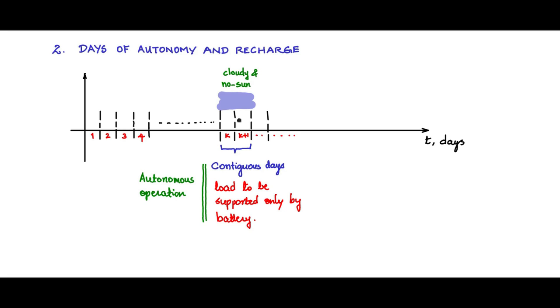It means it is operating by itself without the help from solar or the PV. Which means the battery has to be rated to support the load for as many number of days a particular place needs. So this is called the days of autonomy and we will give a symbol na.